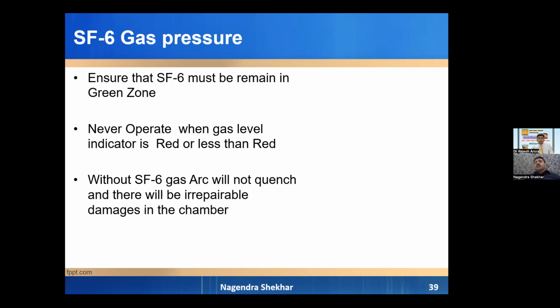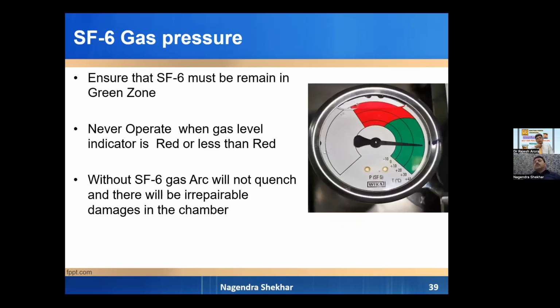So how do we ensure proper working of our SF6 RMUs? Ensure that SF6 gas pressure is always in the green zone. Never operate if it is less than green zone or in the red zone. If gas is not there in the insulated chamber, the arc will not quench, resulting in failure of the RMU. So this is our gas pressure meter. We have to ensure that it is always in the green zone.